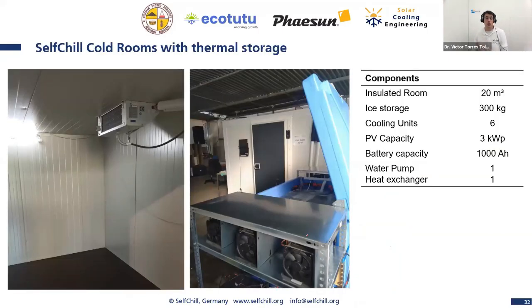Let's have a look how it looks in reality. So here you see the insulated room on the left. This is the cold room itself. Here we get cold water, and here we get cold air out of the heat exchanger. You see here the thermal storage, the ice storage. You see here ice at 0 degrees, right? Then you see the cooling units here.